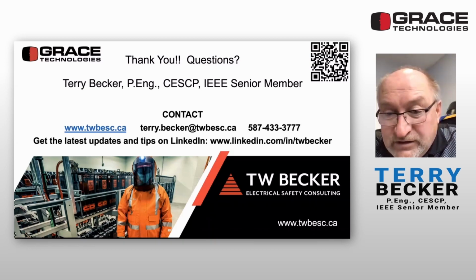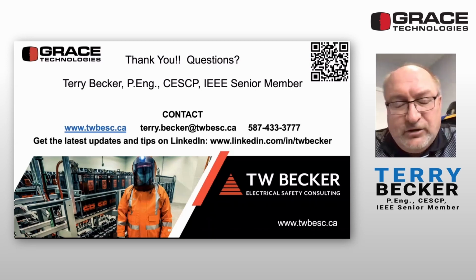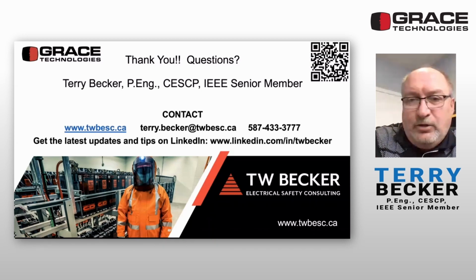And the last question says, previously interpretation of opening gear requiring arc flash and a permit. How can we get clarity on the real interpretation? Folks will ask, where's that exemption written? When it's specifically not, which caused confusion to begin with. The two-level runs to be counterproductive. If I have 13 cal, I'm not in level 2 PPE, which goes up to 40. That's again where the mix-up has occurred between hazard categories and arc flash PPE categories, because there were a range of ATPVs, right? So drop that whole thing.